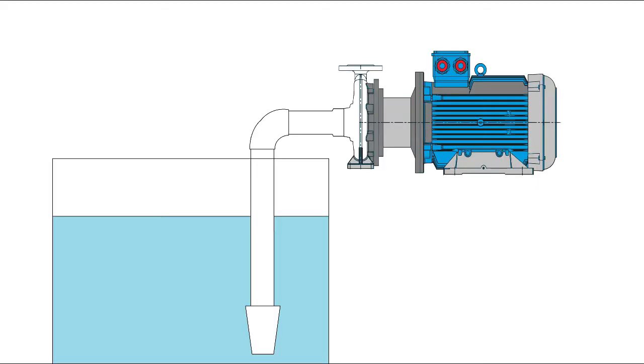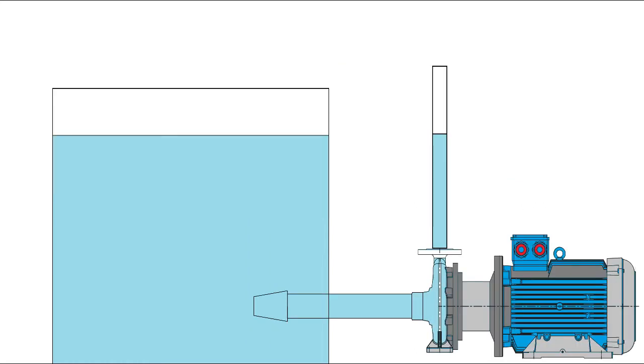The process of filling the pump with liquid is called priming. All centrifugal pumps require liquid in the casing to prime. If the pump casing becomes filled with vapors or gases, the pump impeller becomes gas-bound and incapable of pumping. To ensure that a centrifugal pump remains primed and does not become gas-bound, most centrifugal pumps are located below the level of the source from which the pump is to take its suction. The same effect can be gained by supplying liquid to the pump suction under pressure, supplied by another pump placed in the suction line.